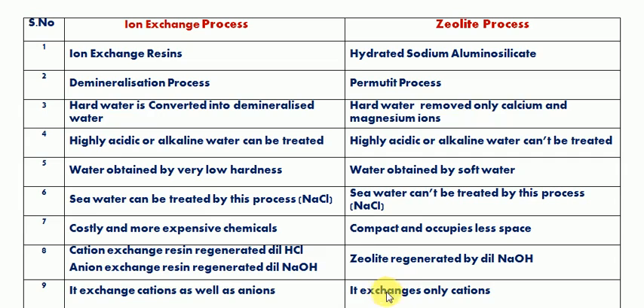In the zeolite process, only cations — mainly calcium and magnesium — are exchanged. The remaining anions such as bicarbonates, carbonates, chlorides, and sulfates remain in the water in the form of sodium salts of their respective acids.